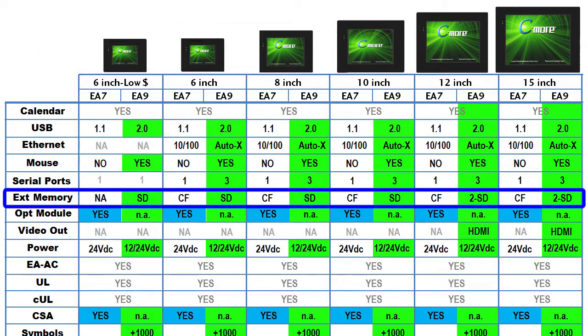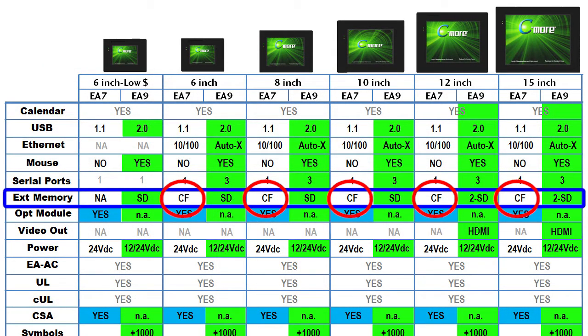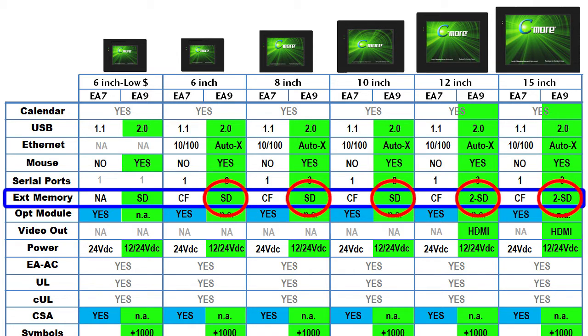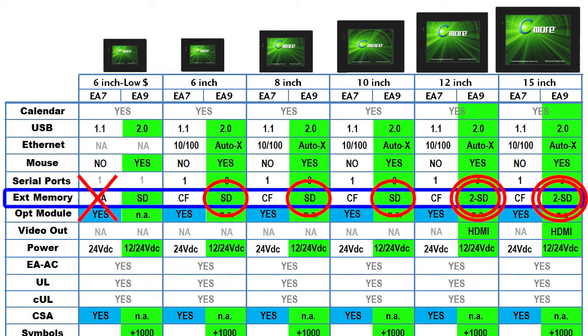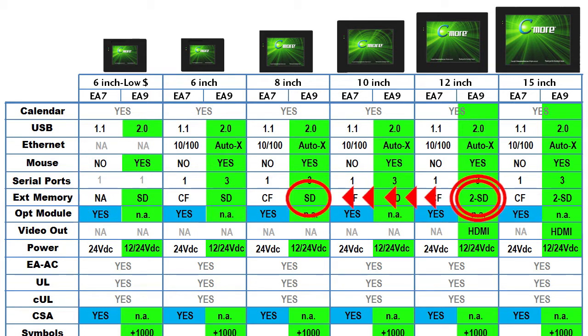The original C-mores relied on compact flash memory for external storage. The new panels use SD cards and the two larger panels have two SD card slots and while the original reduced cost C-more didn't have any external memory, the new reduced cost version does. If you try to downsize from a larger panel to a smaller one that only has one SD slot, the software will automatically remind you to change your project from SD2 to SD1 if you are using that second card slot on the larger panels.